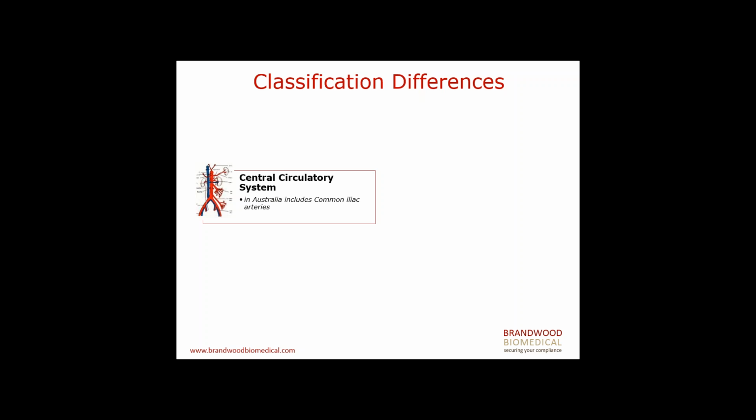So this particular difference can cause a bit of hassle because sometimes notified bodies might be hesitant to include Class 2B products on the design examination certificate, but TGA may grant approval and set a requirement that they would like to receive the design examination certificate with those products included within a certain time frame. But that's one of the examples of differences in classification between Australia and Europe.